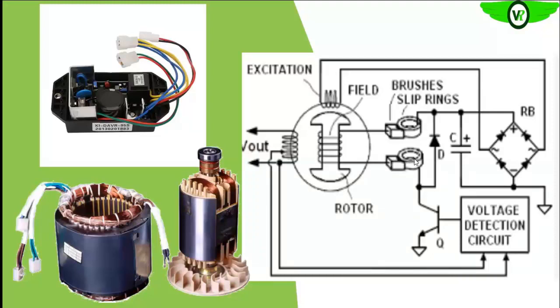After disconnecting it from the slip ring, you will have a reading. But if you reverse it, that is placing your red probe here and your black probe here, there won't be any reading, okay? The phase to phase, you still don't expect to have any reading at all on the phase to phase, okay? So that is how you can use the digital multimeter to test the AVR of your generator, okay?